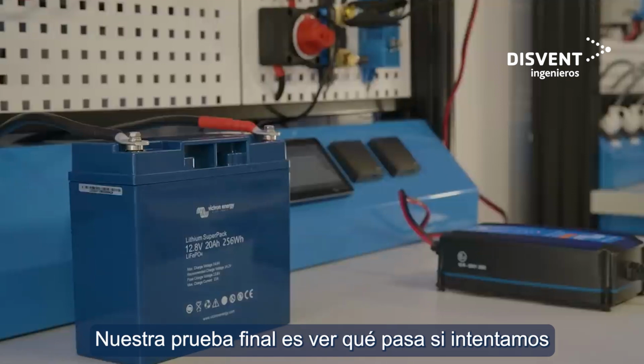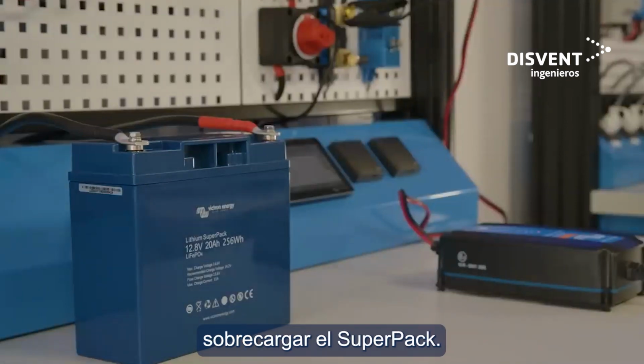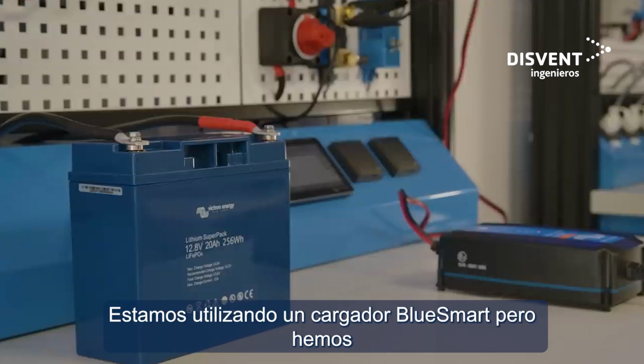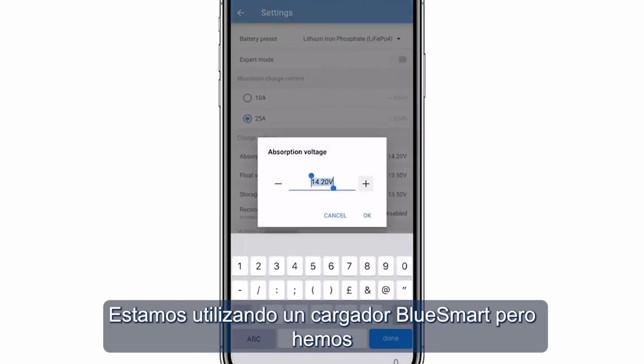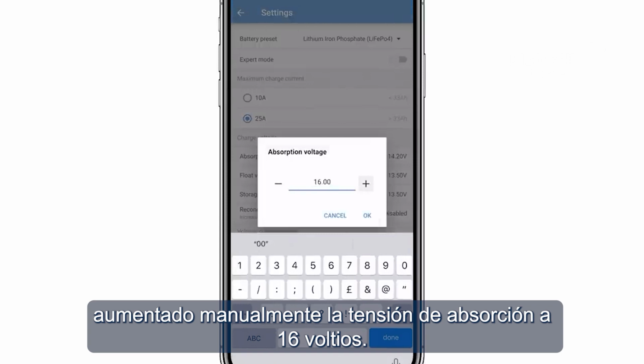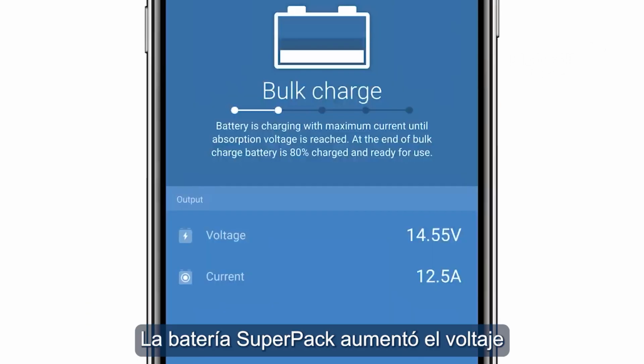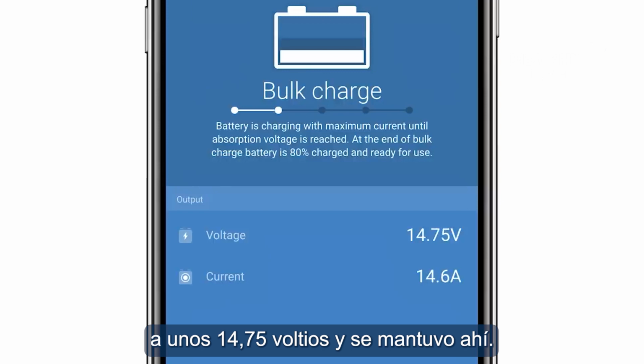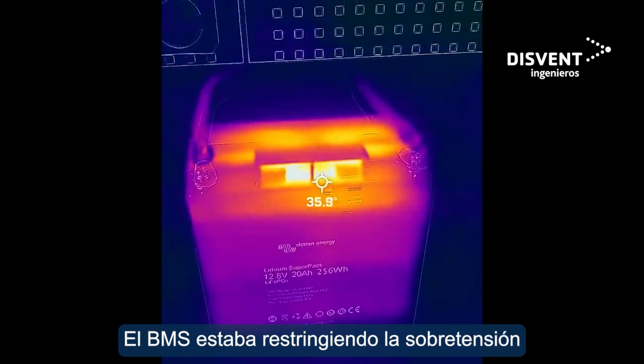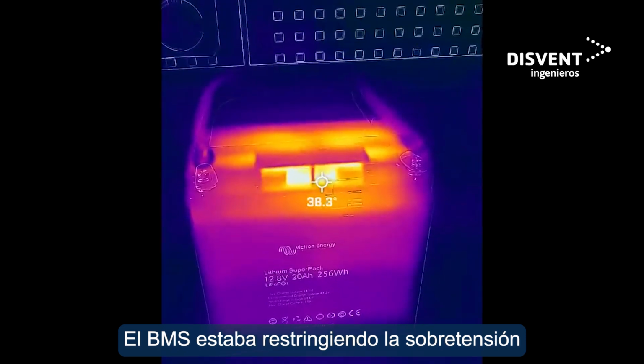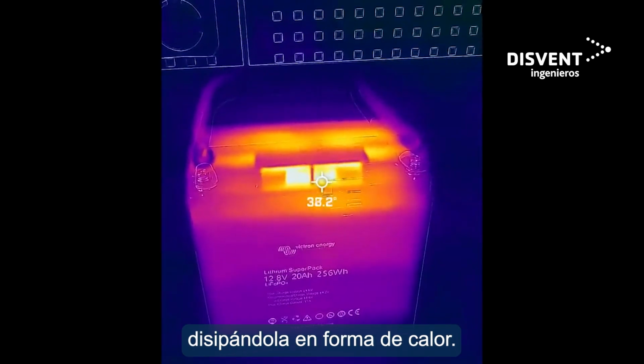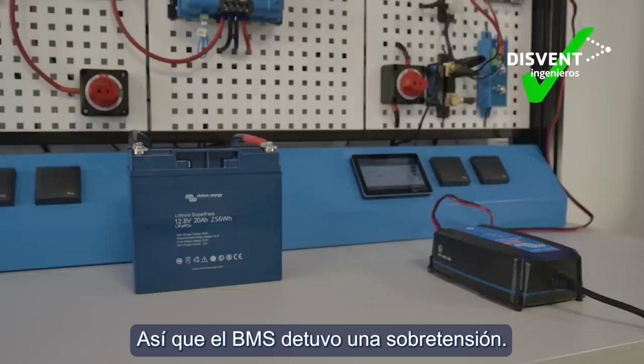Our final test is to see what happens if we try to overcharge the SuperPack. We are using a Blue Smart charger but have manually increased the absorption voltage to 16 volts. The SuperPack battery increased in voltage to around 14.75 volts and stayed there. The BMS was restricting the overvoltage by dissipating it as heat. So the BMS has stopped an overvoltage.